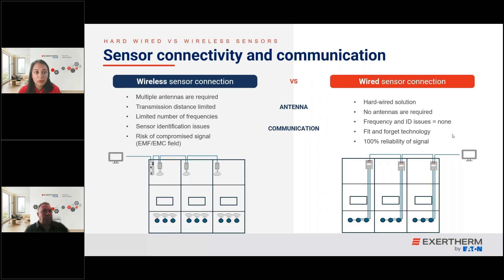Yes, there are wireless sensors and there are wired sensors, but let's look at how connecting those sensors into a system works. If they're wireless, you need antennas, and in a lot of cases, for most wireless sensors, you actually need multiple antennas within the panel. Transmission distance of the actual sensor on a lot of technologies is quite limited, so your sensor has to be within, in some cases, centimeters of that actual antenna.